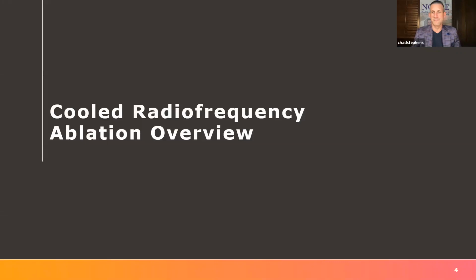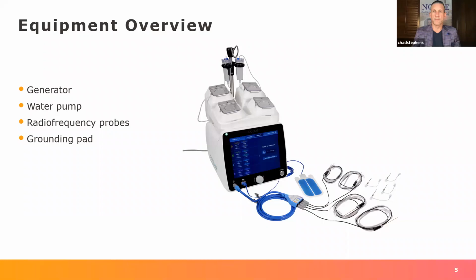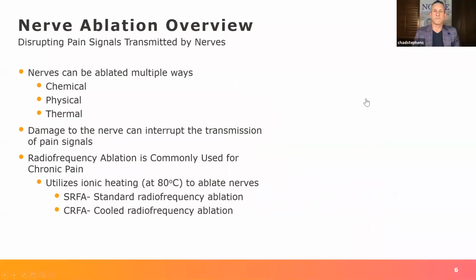So I'm going to go through a quick background of what cooled radiofrequency ablation is, just to ground everybody. This is the equipment. This in the center here is the generator, and on top of the generator you will see some pump heads. Those are utilized for the water pump. You also have radiofrequency probes on the bottom right of your screen, and those are used to address the nerves that are transmitting pain. Additionally, there's a grounding pad, this blue area here in the middle, which is also required to do radiofrequency ablation procedures.